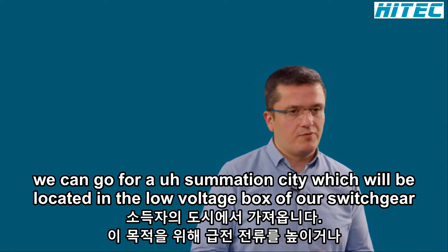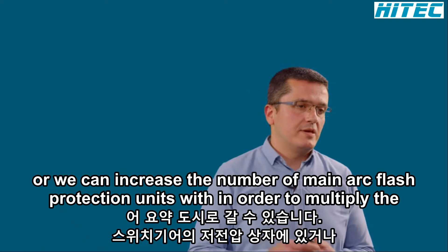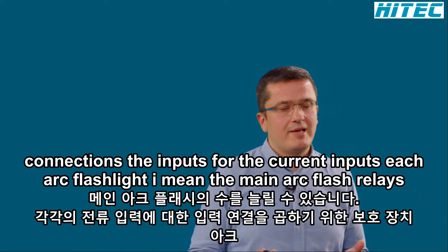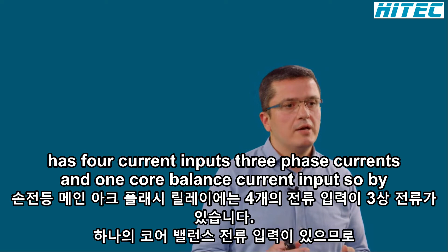As I've told, we don't only rely on light for detection of the arc, we also await an overcurrent signal. This signal is taken from the CTs of the incomers. If there is more than one incomer, we need to sum up the feeding current. For this purpose, either we use a summation CT located in the low voltage box of our switchgear, or we increase the number of main arc flash protection units to multiply the current inputs. Each main arc flash relay has 4 current inputs: 3 phase currents and 1 core balance current input. By utilizing these inputs, we get the overcurrent signal.